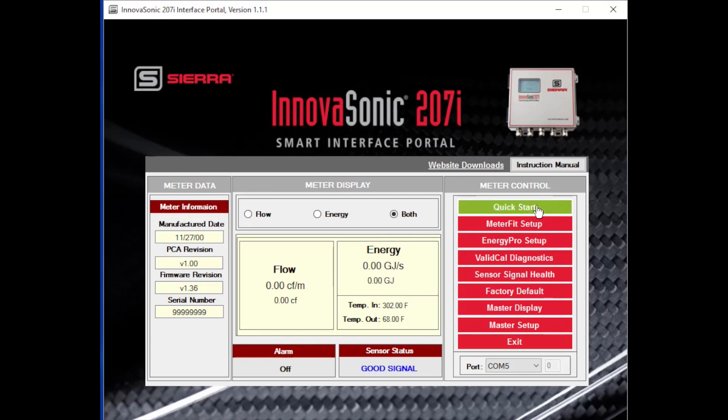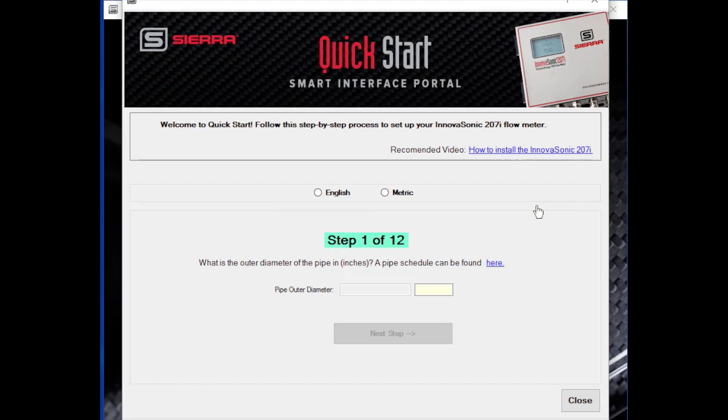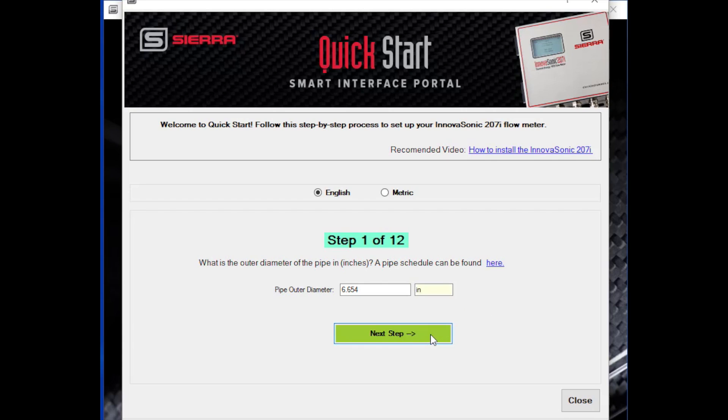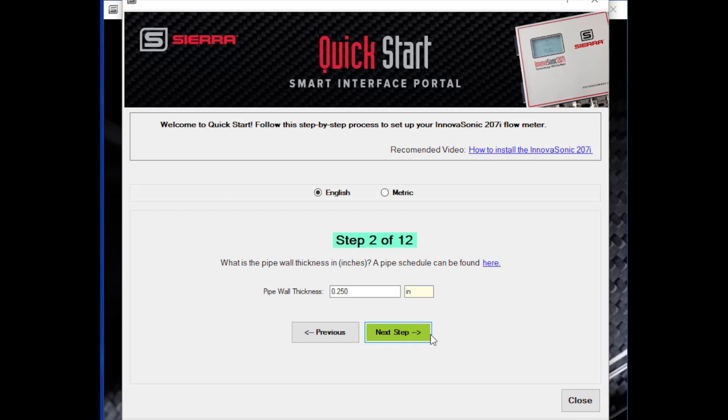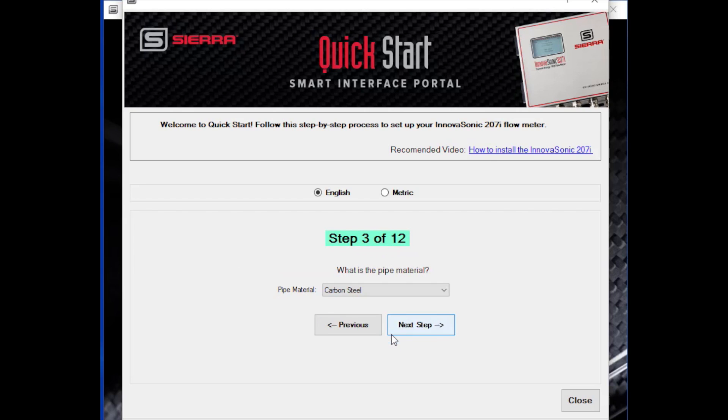So we're going to select the Quick Start button. Select whether you're using English units or metric units. Step one is setting up the pipe outer diameter. So you need to know what the pipe outer diameter is. You enter that number, proceed to the next step. Then it's going to ask you what the wall thickness is. You can look up the wall thickness if you know the pipe schedule. You can measure the wall thickness if you have a thickness gauge. Enter the pipe wall thickness. Proceed to the next step.